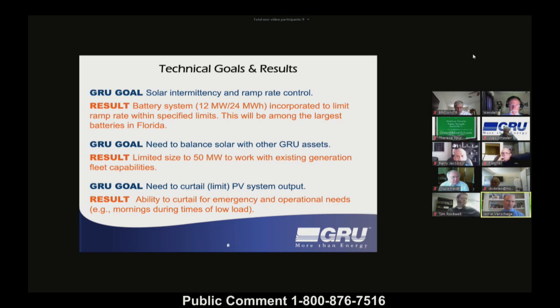GRU worked with the engineering firm Burns & McDonnell to evaluate how much solar capacity could be added to the system. The study evaluated GRU's area control error, or ACE, which Tom talked about a little, under many different scenarios. This ACE is a measure of how well GRU matches its electrical demand with its electrical supply without pushing or pulling energy to or from neighboring utilities.